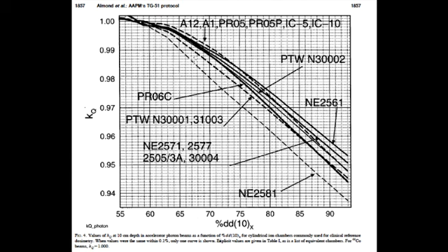So in our clinic, we have this beam here at 67% PDD, and you go up and find your chamber, and you read off what the KQ factor is. So for example, it might be 0.994, let's say, for this chamber. And then you use that for your formula. Okay, so it's a relatively simple protocol to use. All these curves are determined by Monte Carlo calculations. They're very accurate, and somebody's done all that work for you.